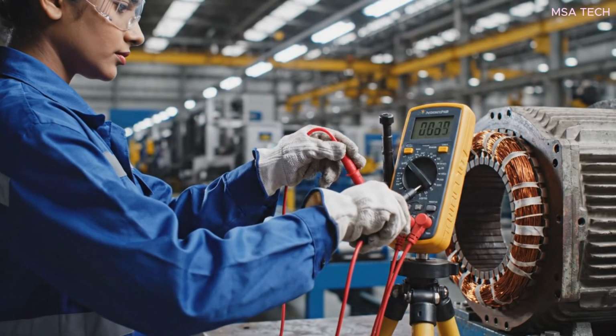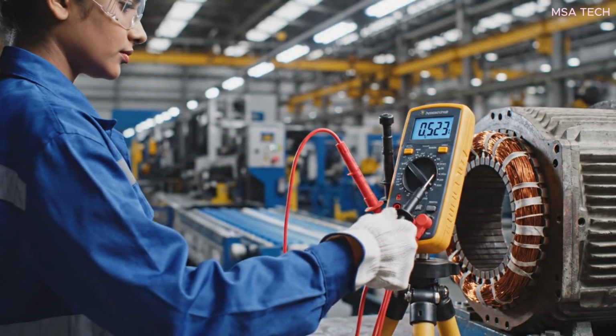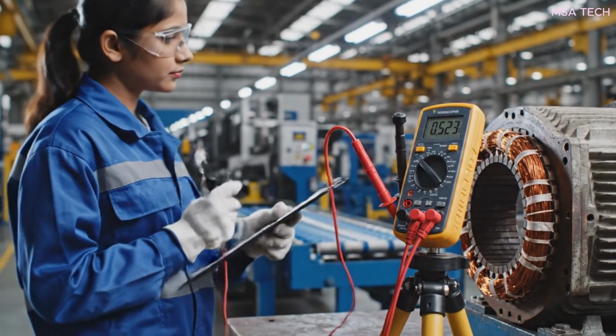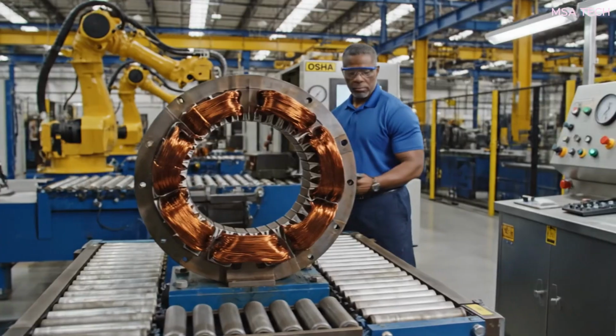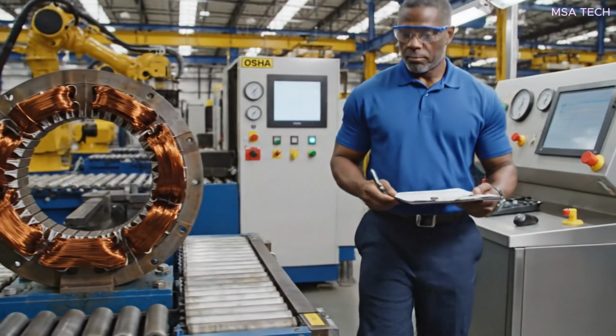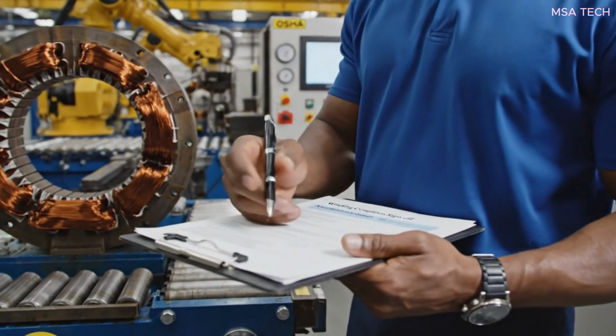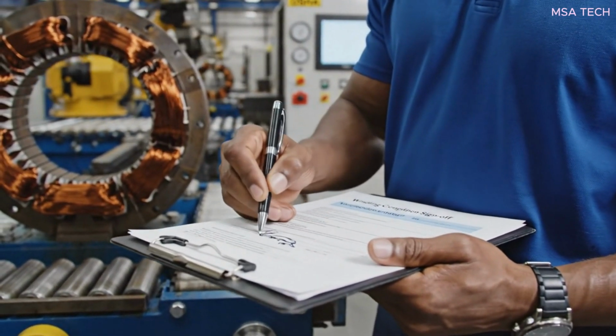Resistance testing ensures correct electrical continuity and balance. The completed winding is inspected and then approved via sign-off, clearing it for the high-voltage insulation and impregnation process.